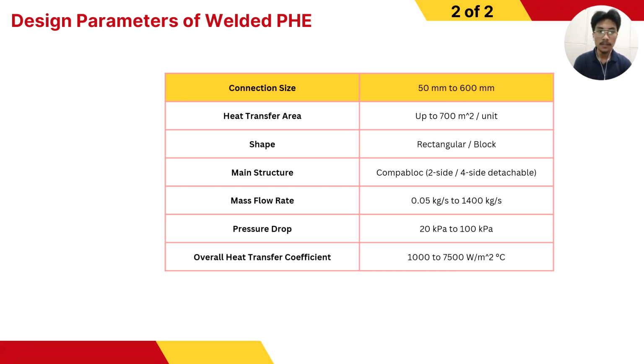Next up is mass flow rate. So according to Alfa Laval, which is one of the popular manufacturers of plate heat exchangers, the mass flow rate normally ranges between 0.05 kilograms per second to 1,400 kilograms per second. For pressure drop, it ranges from 20 kilopascals to 100 kilopascals.